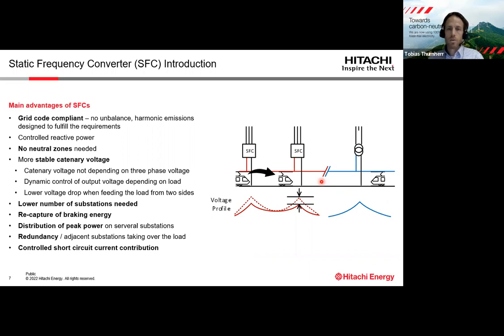The peak power is also distributed on several substations. So per substation, we have a lower peak power. So the substations need to be dimensioned for not the same peak power. We have better performance in terms of redundancy, because if one substation fails, then the adjacent substations can immediately take over the load, so you will not have an interruption of the supply of the catenary.